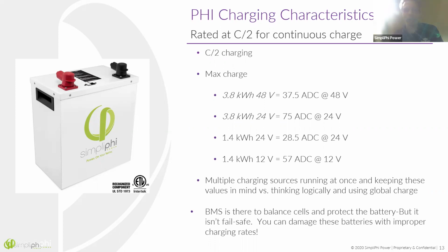Now, because the 24 volt version of this battery has a larger total current rating, that battery will charge at a higher current, 75 amps DC, but it's still the same power because it's half the voltage. So we're still looking at 1.9 kilowatts for your charging equipment per battery. If you have 2 batteries in parallel, it would double. If you have 5 batteries in parallel, it would go up by a factor of 5. So 37.5 amps is the limitation for these most common 48 volt batteries. The smaller 1.4 kilowatt hour batteries charge, again, at half the total current rating of the battery. So half of that 57 would be 28.5 amps DC. And then for the 12 volt version, you're looking at that full 57 amps DC at 12 volts.